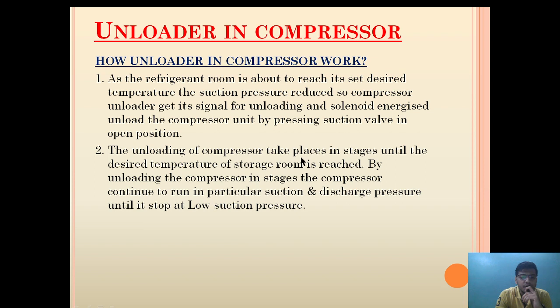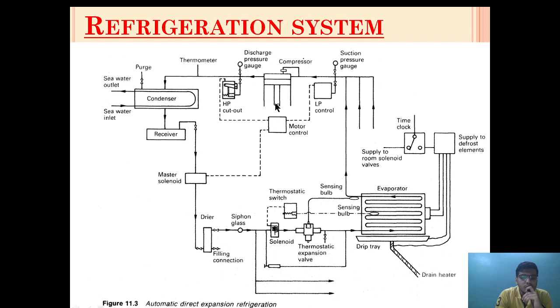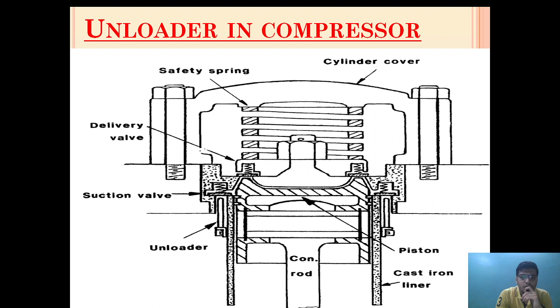The unloading of the compressor takes place in stages until the desired temperature of the storage room is reached. By unloading the compressor in stages, it continues to run at a particular suction and discharge pressure until it trips at low suction pressure. The compressor will continue its operation until the other room temperatures are also attained. Once all room temperatures are attained, a pressure is reached where it cannot be operated further — at that point, the LP trip will automatically get reset as the pressure in the line increases. I hope the concept of the unloader is clear.